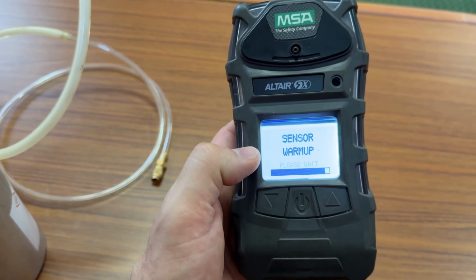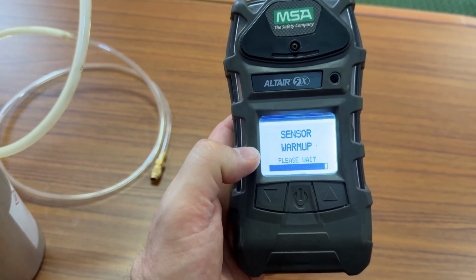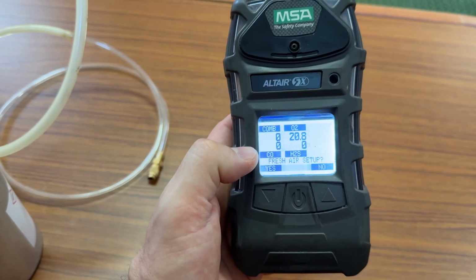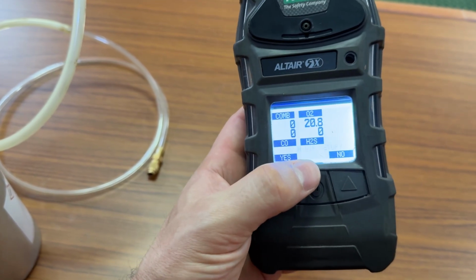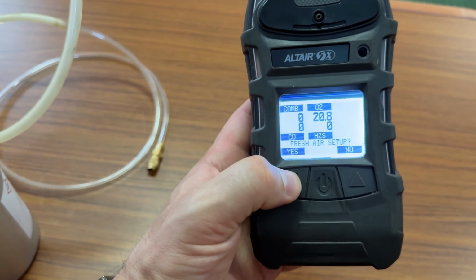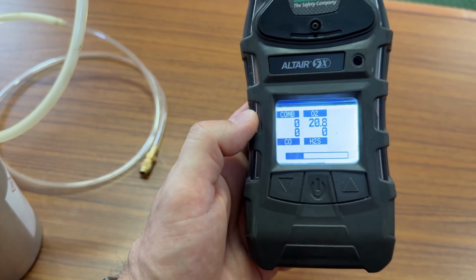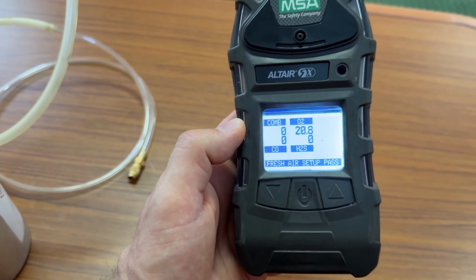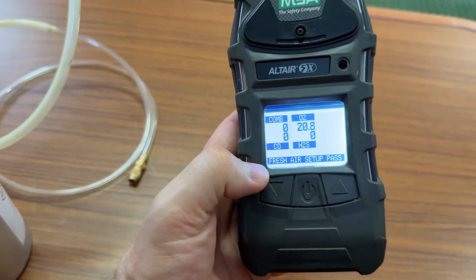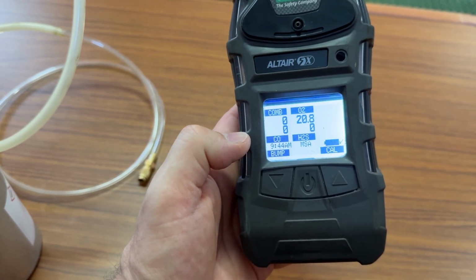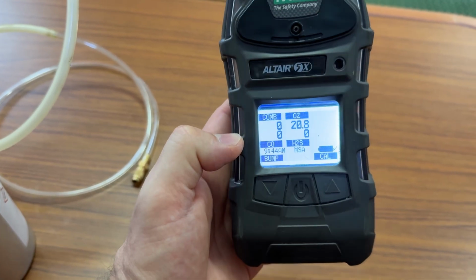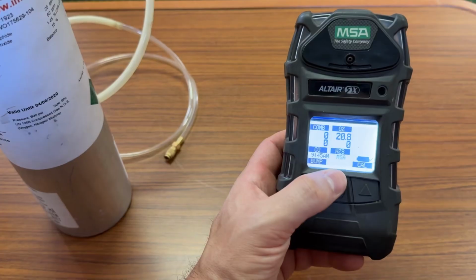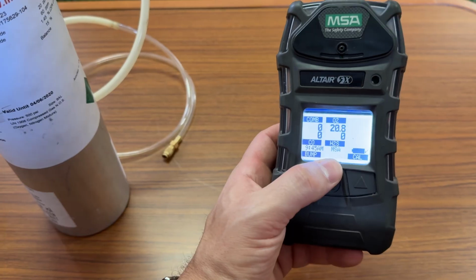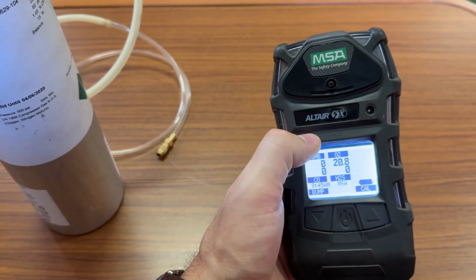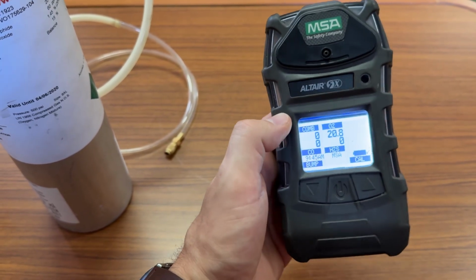He is making again self-tests, checking the sensors, and fresh air setup. Before using it again, before you go into some enclosed space, you are switching it on and making fresh air setup. Setup is pass, and after that you can go to the enclosed space. So this is all about calibration of gas detector MSA model Altair 5X.